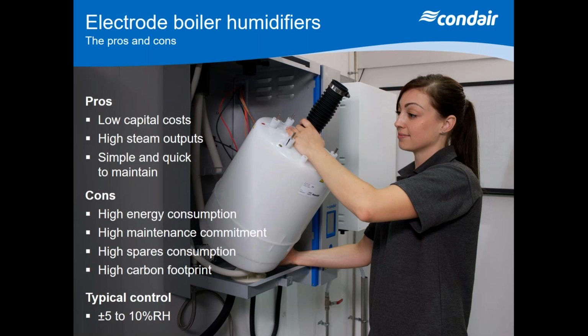So these systems will just purely work on the basis of introducing raw mains water, and I mean raw mains water, to allow the electricity to conduct between each electrode to boil the water and produce steam atmospherically. Very similar to your kettle at home. So very, very simple system. They're very quick and easy to install on the wall with a cabinet, water in, drain out, and then your controls are normally in the form of a 0 to 10 volt control signal to drive it up and down. And then they have the enable or disable circuit to switch it on and off with a fan, or if there's a high limit in the supply duct, to switch it on and off.